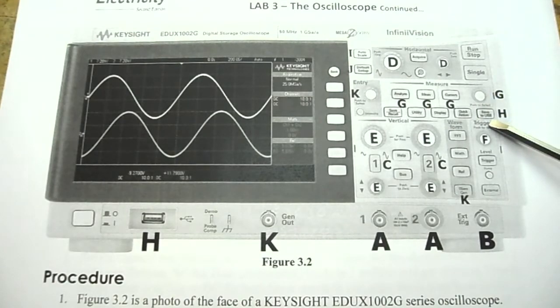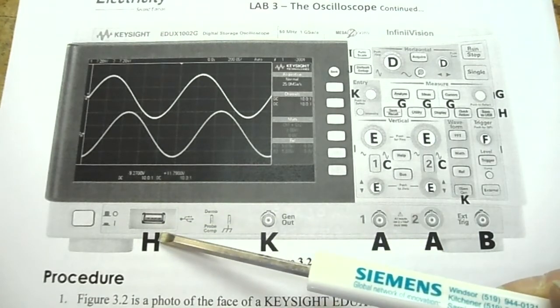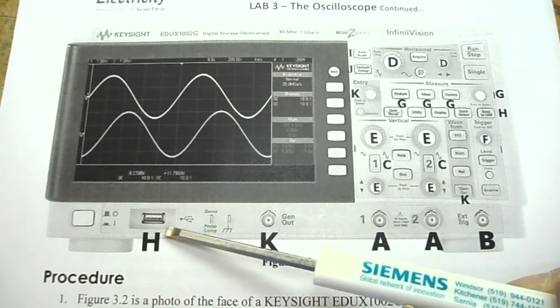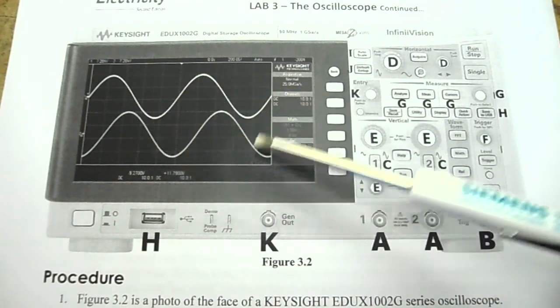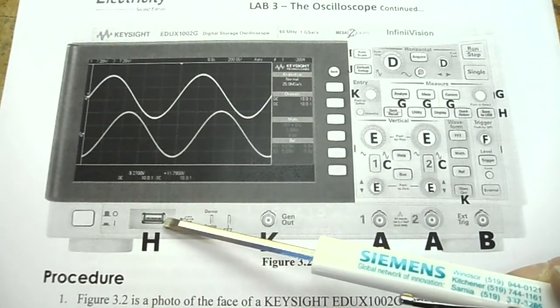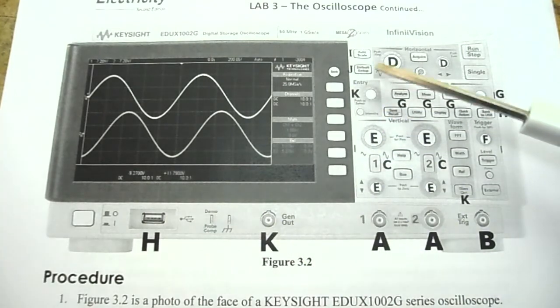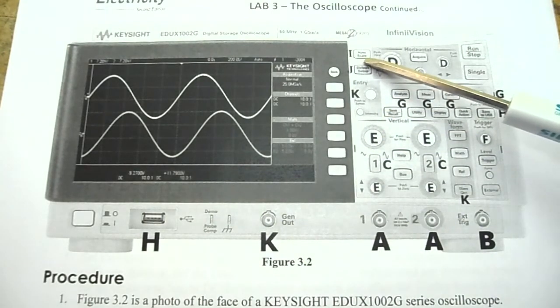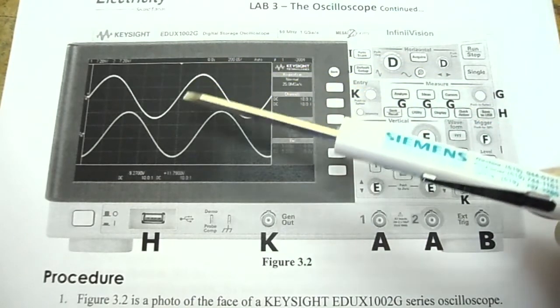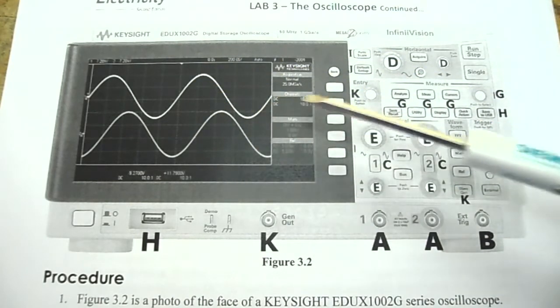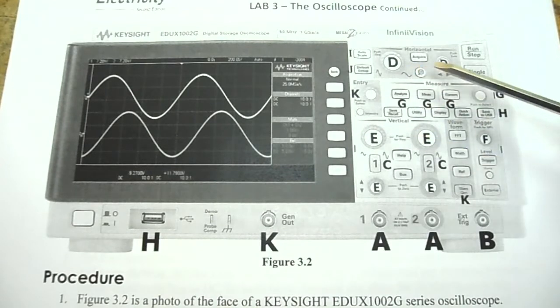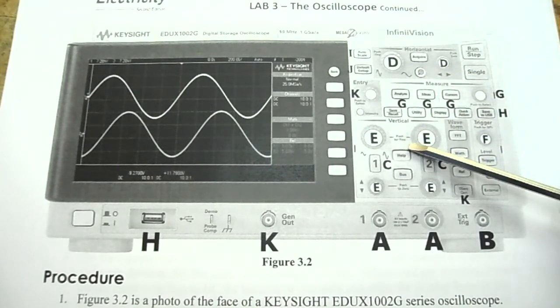H is your save to USB. So we do have a USB connector on here, and if you plug in a USB thumb drive, you can actually save the display onto that USB thumb drive. I is important, autoscale. Autoscale tries to put the waveform correctly on the screen so that you don't have to adjust as many of these controls. Doesn't always work out for you.